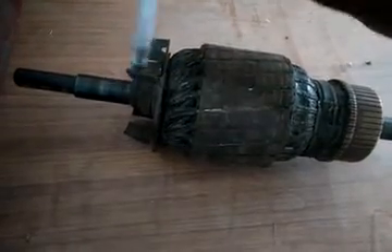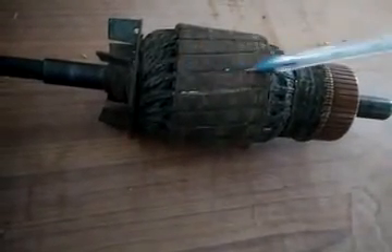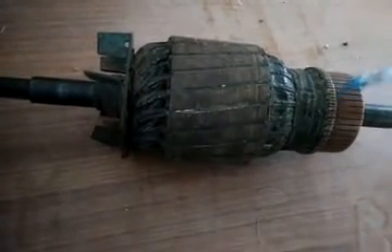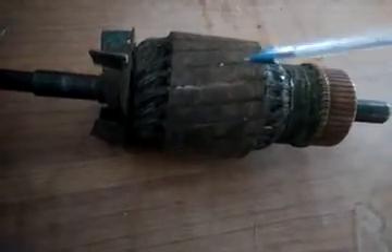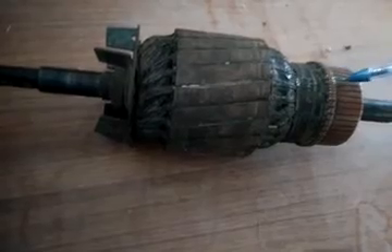There are bearings for easy rotation of the armature. The armature laminations are made with silicon steel, and the winding is made up with copper. Copper windings start from the open legs of the armature laminations at the commutator segment. Using lap winding, the other end will be connected to another commutator segment. Lines are made in between each commutator segment, and mica insulators are placed in between to insulate each segment. This is the overview of the DC machine.